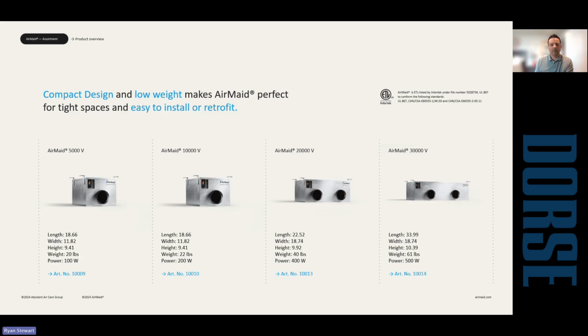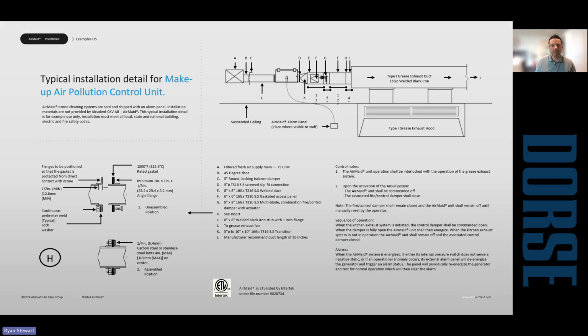And these are pretty small in comparison. So again, they're easy to retrofit. And this just gives you an idea of how it ties in. So you'd have this tap into the grease duct right near where the hood is.